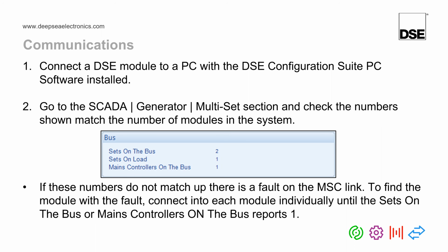One thing to remember though is what many people do to test the MSC link is they remove the wire from the back of the DeepSea module and then reapply it to see if the alarm appears and then disappears. The DeepSea module will only give you an MSC failure alarm if the module's MSC link was working before and then has failed. So for example, if you were to turn on a DeepSea module with no MSC link connected, you would not see an MSC failure alarm. That is because there was no working MSC when the module powered up. So just keep in mind that the MSC failure alarm only appears when there was a working MSC link and then it disappears.